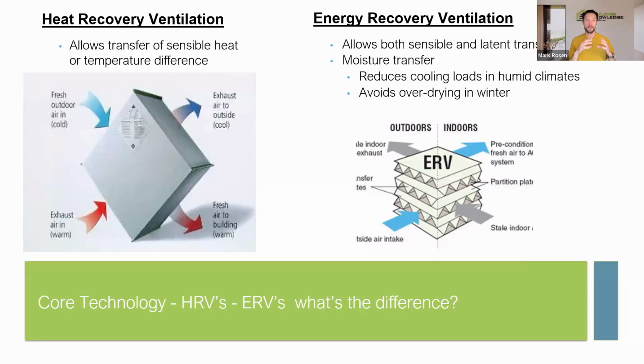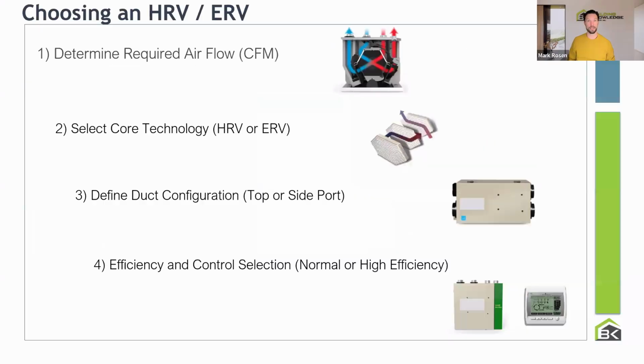It's in this core that the primary difference lies between heat recovery ventilators (HRVs) and energy recovery ventilators (ERVs), sometimes called enthalpy recovery ventilation. The key difference: an HRV only transfers and recovers heat from the outgoing air, and any resulting condensation is drained and discarded. An ERV transfers both heat and moisture in the core, sensible and latent energy, recovering heat and some humidity to prevent over-drying in winter, something we constantly fight against in Canadian winters across many locations.